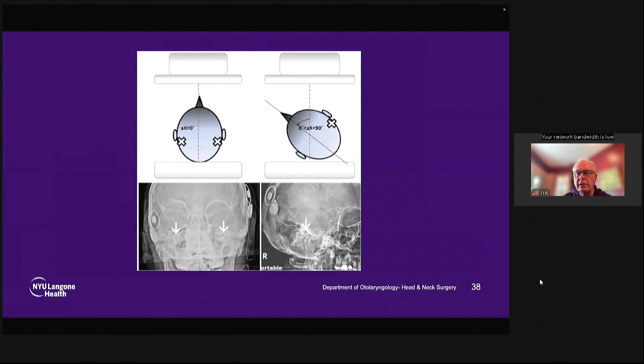So we looked recently at some reimplantation data at NYU. Our failure rates have overall decreased from a reported 6 to 15% in the literature. The AB field action plan, and a lot of that has to do with improvement in implantation techniques, improved manufacturing quality control, and also manufacturers responding to our cause of failure analysis. In other words, if a certain model of device has a certain number of failures, then in the next generation, if they can figure out why that failure occurred, which is almost always a hermeticity issue where the electrodes come out of the device, they can fix that and build that out.